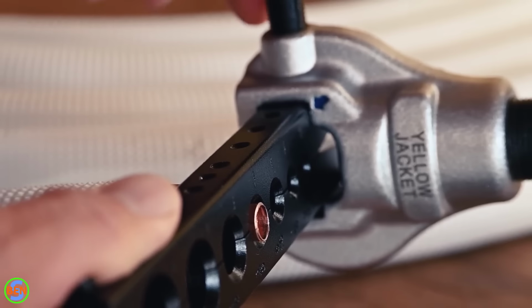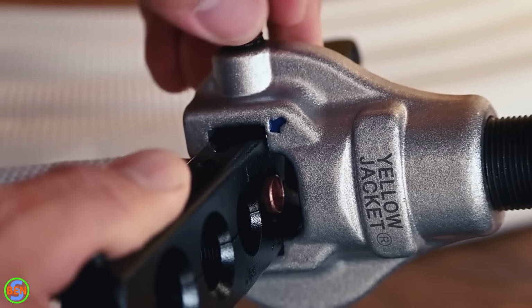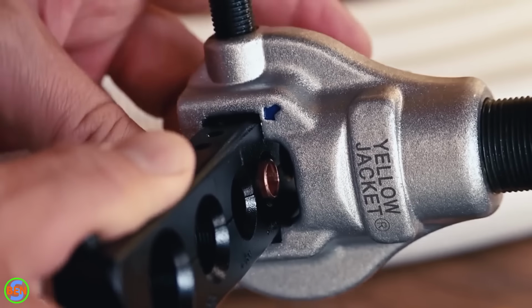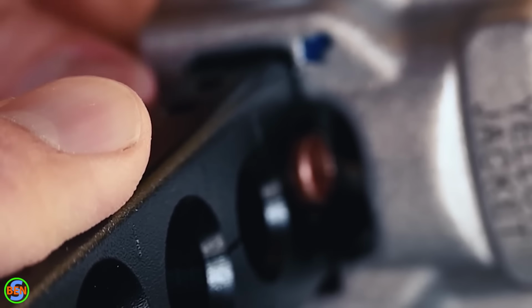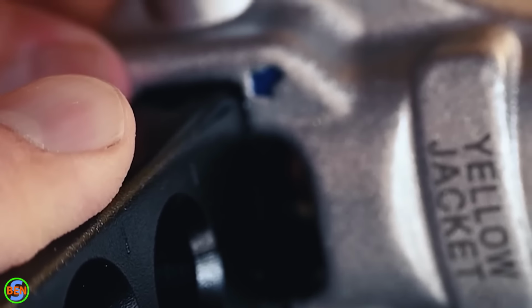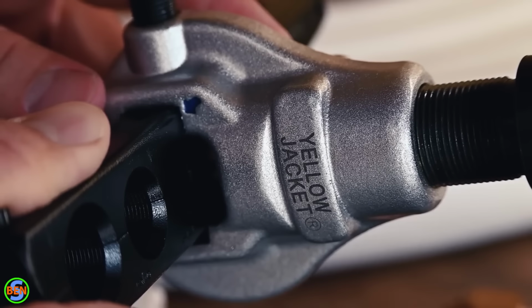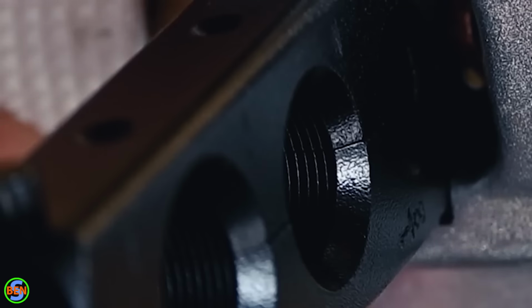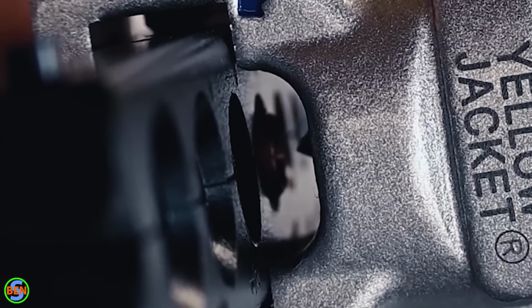Now we're going to slide the rest of our flaring tool over the spot where we want to create our flare, and you can see this little arrow should line up with this line right here on the flaring tool so that it can clamp down properly. So we just tighten it and make sure that there's no gap right here between the two halves of the tool. Now we're ready to tighten down.